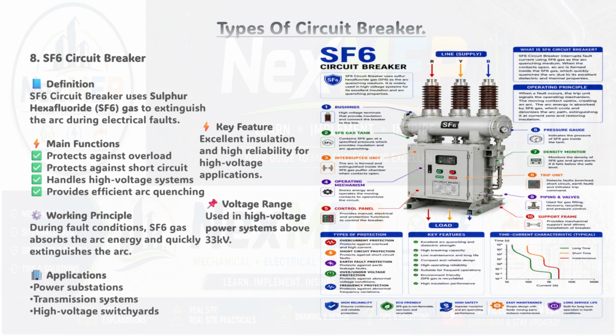Type 8 is the SF6 circuit breaker, and this is where we step into high voltage territory. SF6 stands for sulfur hexafluoride, which is a special gas used as both the insulating medium and the arc quenching medium. When a fault occurs, the trip unit signals the operating mechanism. The moving contacts open inside the SF6 gas chamber. The arc that forms is immediately absorbed and extinguished by the SF6 gas because of its excellent dielectric and thermal properties. SF6 breakers are used in high-voltage power substations, transmission systems, and high-voltage switchyards anywhere above 33 kV.